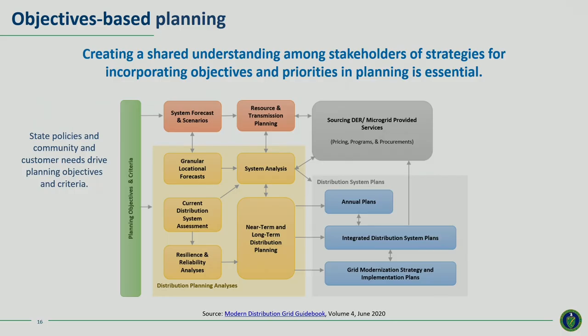The second element is developing system-wide forecasts and scenarios, to ensure consistency with bulk power system planning — which could include iteration with ISOs and RTOs. For example, folks from Illinois work with their RTO to make sure there's sensibility between the utility's forecasts for DERs and loads and what the ISO and RTO are doing. Utilities should consider multiple scenarios for loads and distributed resources on the distribution system, because they have impacts on the need for and timing of bulk power system investments, such as investments in transmission.